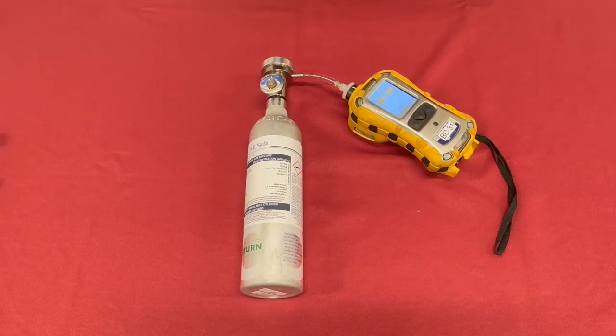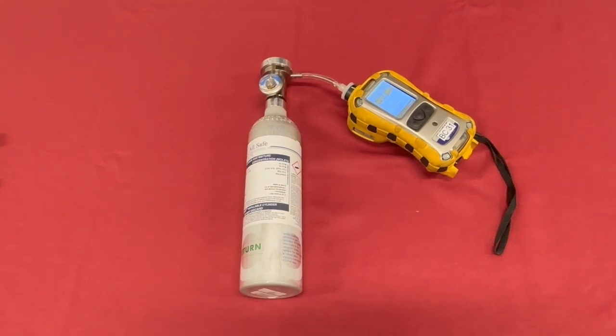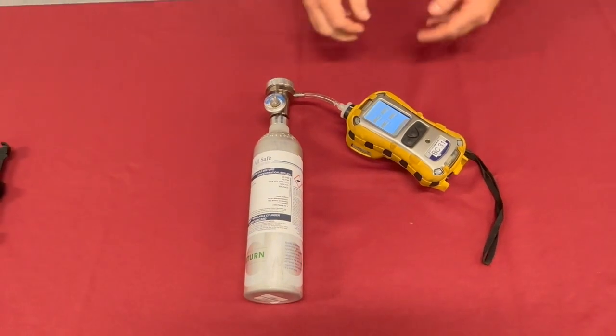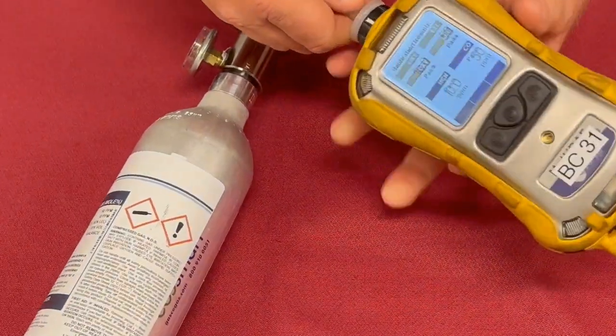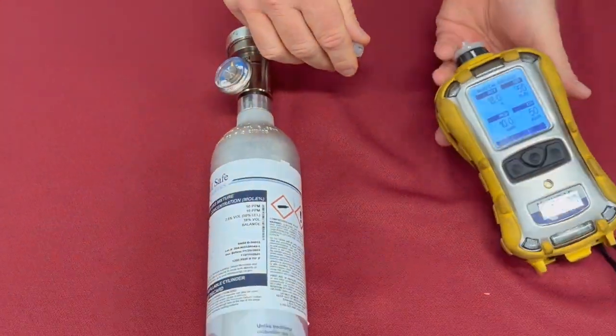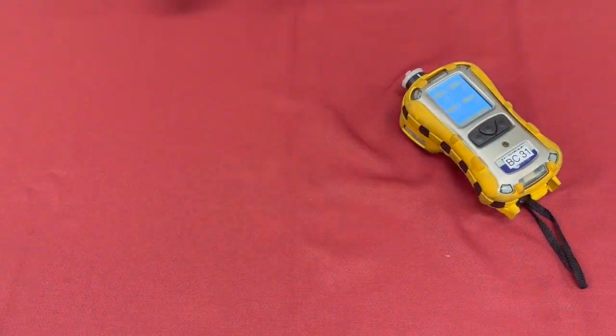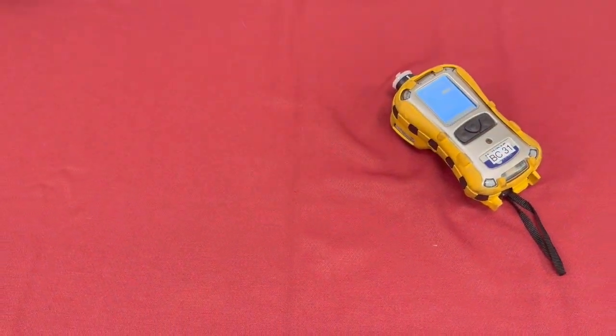Okay, we're winding down to the end here, and we'll see if the meter has adjusted all of the sensors to this known calibration gas. It will come up with 4 passes. If something is wrong, it will fail it. All right, we have 4 passes, so we can move on. All we do is remove the gas, and we'll get another calibration gas.